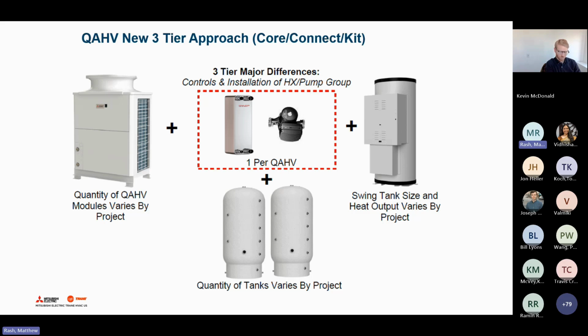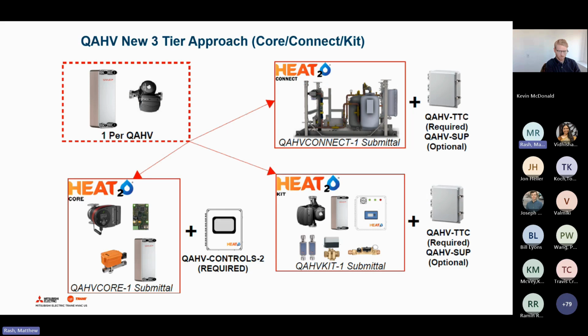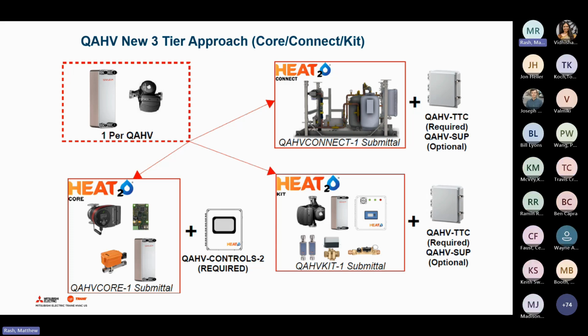That being said, this is the hot water outlet on the unit itself, and it always has to be applied with a separation heat exchanger. So this unit isn't necessarily potable rated. It isn't NSF, so we always apply this with the separation heat exchanger. And then typically the piping between the QAHV and the separation heat exchanger indoors is going to be filled with glycol, up to 30% propylene, max in most climates, is what we allow.